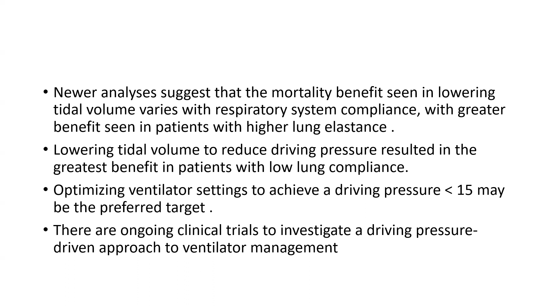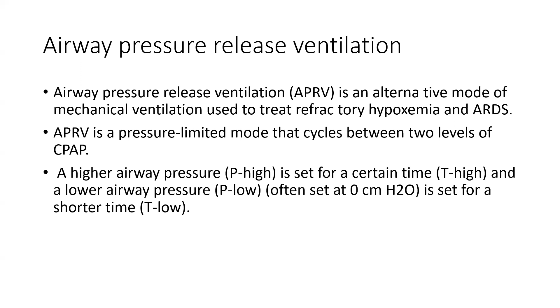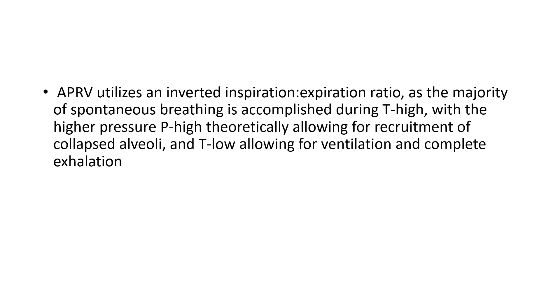Now the next is airway pressure release ventilation. Airway pressure release ventilation is an alternative mode of mechanical ventilation used to treat refractory hypoxemia and ARDS. It is a pressure limited mode that cycles between two levels of continuous positive airway pressure: the higher airway pressure is set for a longer time, and the lower airway pressure is set for the shorter time. APRV utilizes an inverted inspiration to expiration ratio, as the majority of spontaneous breathing is accomplished during the T high with higher pressure, theoretically allowing for the recruitment of collapsed alveoli, and the T low allowing for ventilation and complete exhalation.